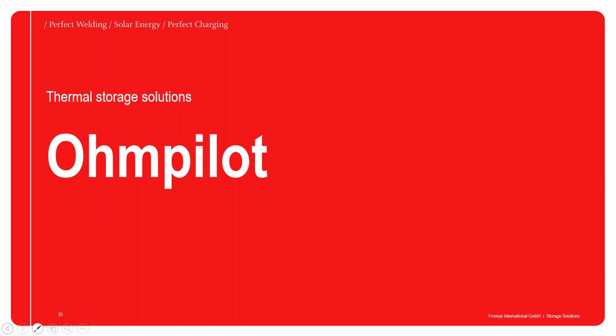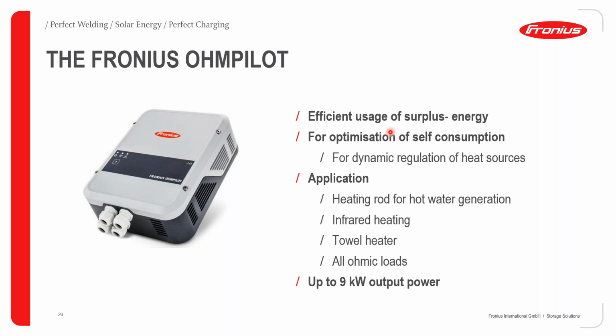Now moving on to the thermal storage solution, which is the Ohmpilot. The Ohmpilot allows for efficient usage of surplus energy. It allows for optimization of self-consumption, and it does this by dynamically regulating a heat source. Some examples of what you can attach to an Ohmpilot: infrared heating, towel heating, any ohmic load, so any load that is purely ohmic. You cannot connect a load to the Ohmpilot if it has some inductance in it. A classic example would be to attach it to a heating rod in a boiler or a geyser, and any excess PV energy that you get throughout the day, whether it is 50 watts or 2 kilowatts, you just take that excess energy and send it immediately to your heating rod in order to heat up your water. With the Ohmpilot, we can have a single phase output of 3 kilowatts, or a 3-phase output of 9 kilowatts max.